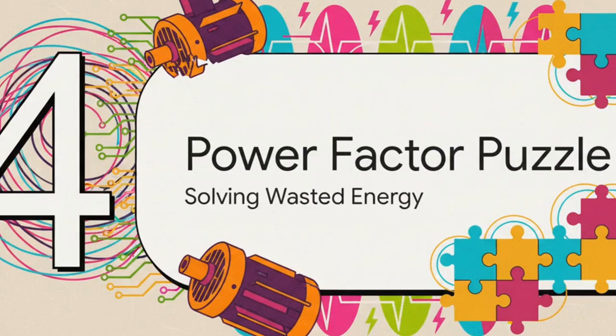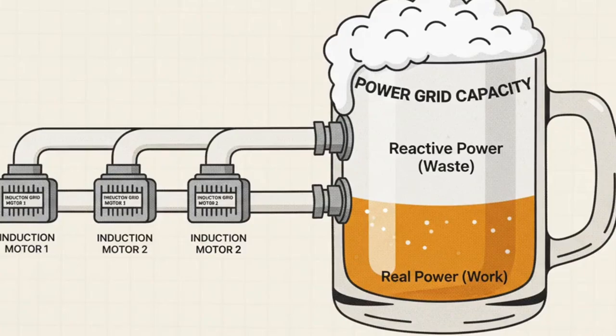Okay, for our final topic, we're going to zoom out. We're going from a single motor to a system-wide problem that motors create, and, surprisingly, a problem that they also solve. This is what I like to call the power factor puzzle. So the problem starts with our good old workhorse, the induction motor. When you get a ton of them running in a factory, they draw a type of power called reactive power. Now, this power is essential for creating their magnetic fields, but it doesn't produce any actual work. It just clogs up the electrical grid. Think of it like the foam on a beer. It takes up space, but it's not what you really want. It just makes the whole system inefficient.